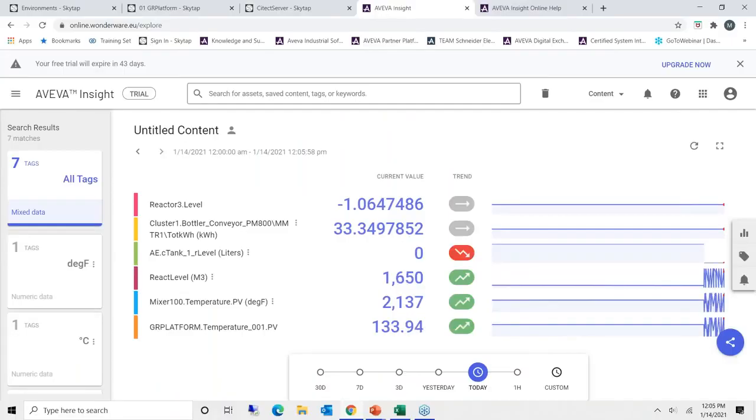But first, I will show you a live demo where I already prepared some data, or tags. The first tag here is connected through a CSV. This is manual data, and I'll show you how to create manual data or how to connect a JSON or IoT gateway. When you have the name of a cluster, that means this is a tag coming from a Citect SCADA. I have a tag coming from AVEVA Edge, another tag coming from InTouch, and another tag coming directly from OI server. Here I'm using a Modbus OI server and TCP. And last but not least, you can see the name of the PC, the computer name, dot the tag name. This one is coming from a historian server.